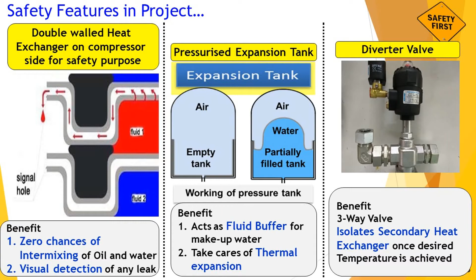Now what are the safety features? While designing, we have put a double walled heat exchanger at the compressor house so as to avoid intermixing of the oil with the circulating water. And there is a visual indication if any leakages are there. We have put a pressurized expansion tank so as to take care of thermal expansion of the fluid, and it acts as a water buffer. The diverter valve on the equipment side: we don't want overheating of the solution, and at a particular set temperature, the diverter valve cuts off the heat exchanger circuit at the equipment side. So thereby we ensured the safety.